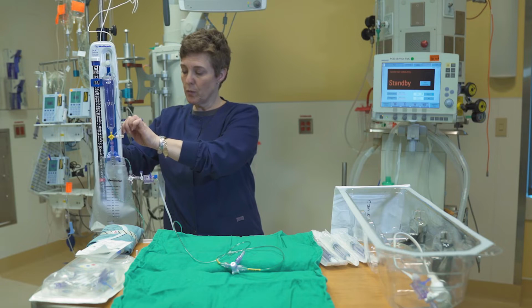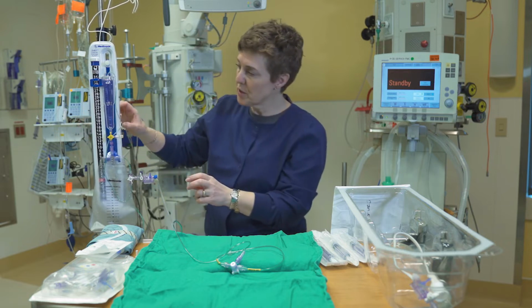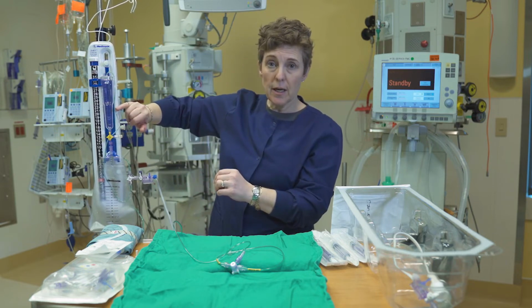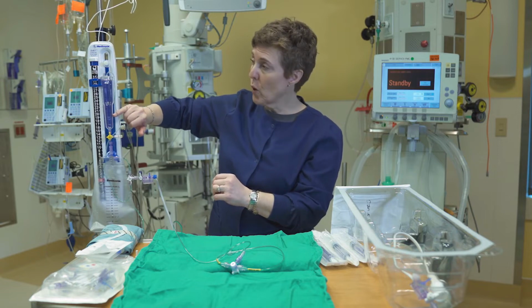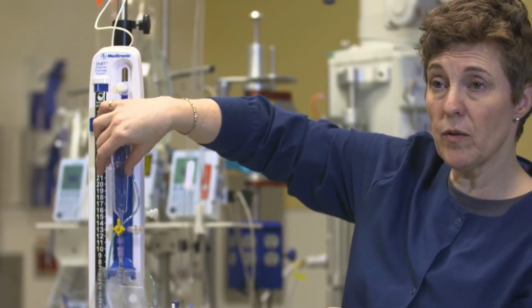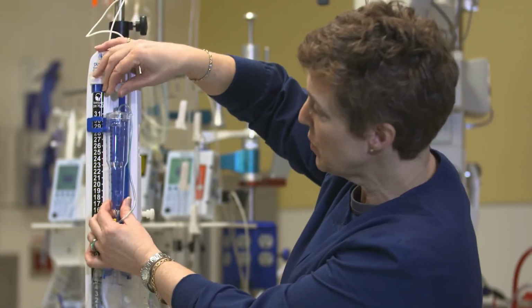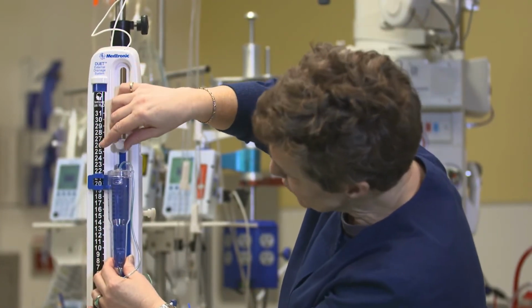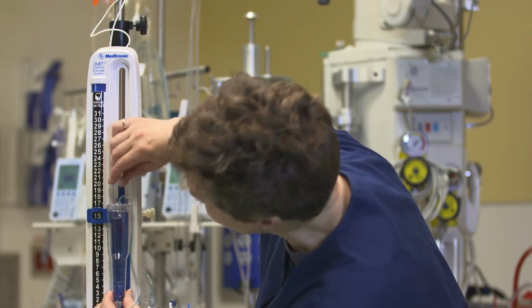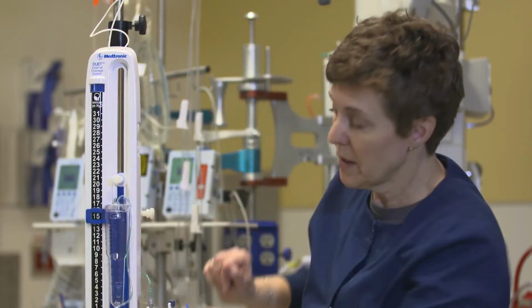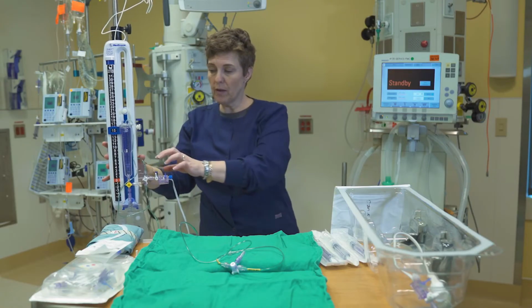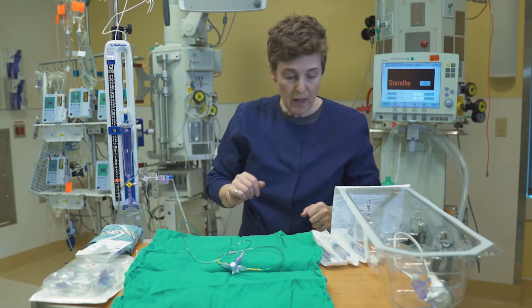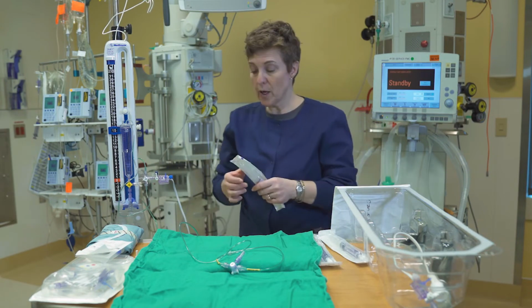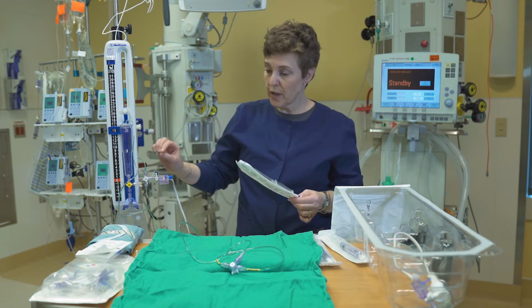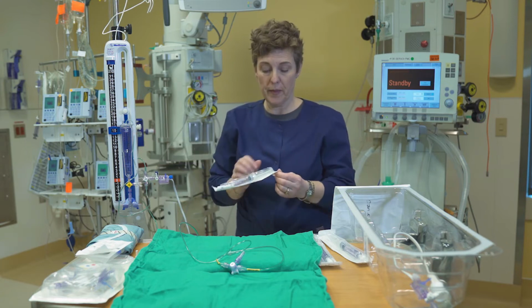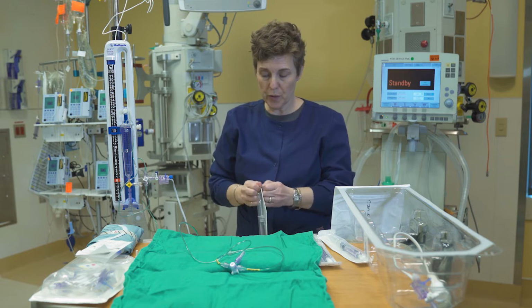Your measure, and it really doesn't matter too much because your measurements, we're going to level it to the patient's foramen of Monro, and then we're going to set our level of drainage according to this piece, which for right now, we'll just set it 15. So then we'll level this to the patient. So the last piece for our setup is to back flush, and we're just flushing this piece. And that's where we're going to use our preloaded syringes.